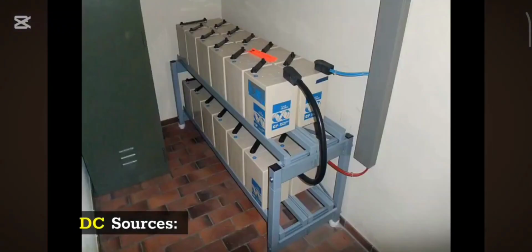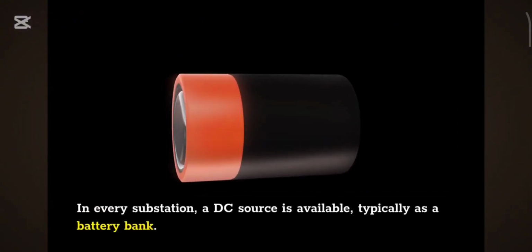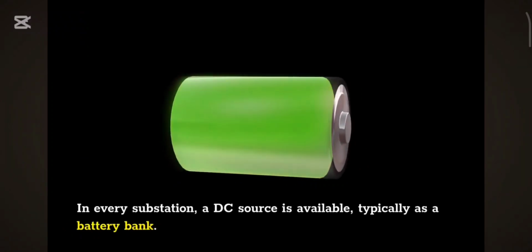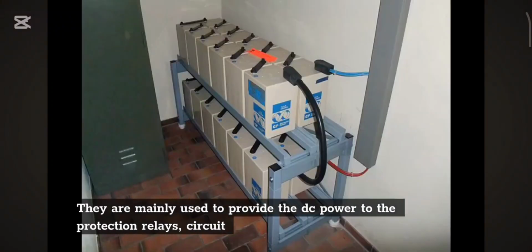DC sources. In every substation, a DC source is available, typically as a battery bank. They are mainly used to provide the DC power to the protection relays, circuit breaker auxiliary power such as close and trip coil, and charging motors.